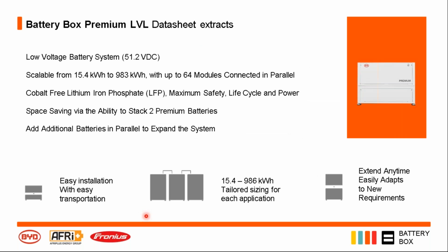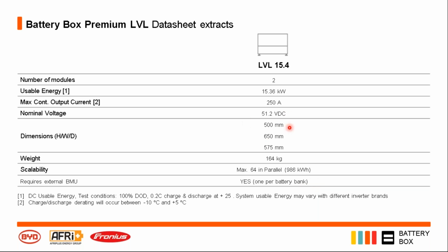Here we've got some LVL datasheet extracts. It's parallel all the way up to nearly a megawatt. It's also the LFP design, and you can stack these one on top of each other. So on a 650 wide by 575 deep, 1 meter high footprint, you can have 30 kilowatt hours in that area. A few little datasheet extracts.